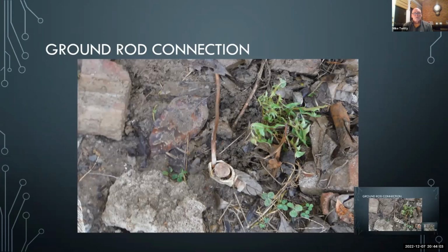Okay, here's a ground rod connection. This is basically what, around in my parts, this is about all we see, if we even see that. Most of the time that gets covered up. But this is an acorn clamp with a ground electrode conductor going into the acorn clamp to the top of a driven, looks like probably a copper, ground rod. There is a proper way to do that. Sometimes you'll see that equipment grounding conductor on the bolt set screw side. That's improper. This one is correct. It goes in that little V-shaped end of the acorn clamp. That's the proper way to do that.